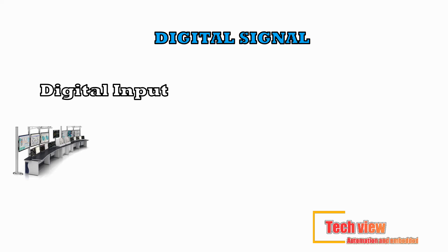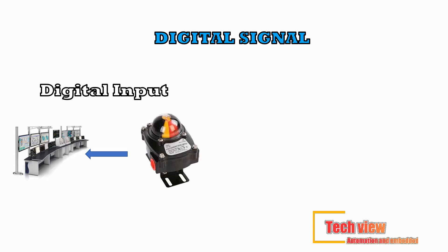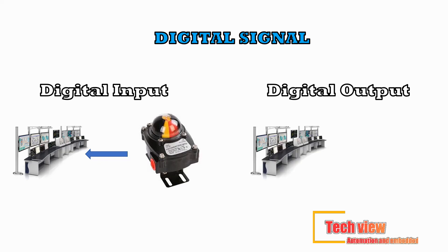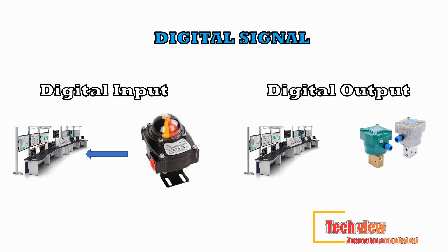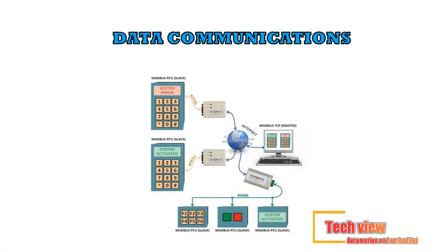A limit switch is an example of a discrete input device because at any given time it is either open or closed. It sends a discrete digital signal to a PLC; this signal can have one of only two values — 0 or 1 — indicating that the device is either off or on, respectively. A pilot light is an example of a discrete output device; it can only be on or off. A discrete output device receives a discrete digital signal from a PLC telling it to be in either one state or the other, and can never be in a state in between on and off.